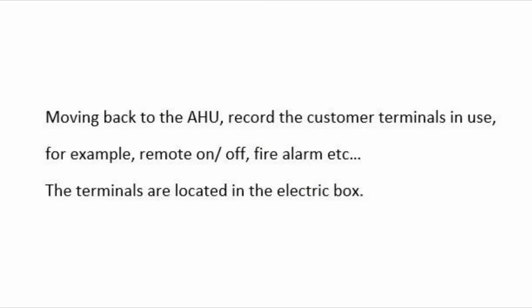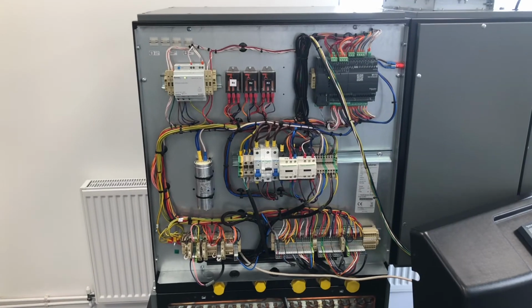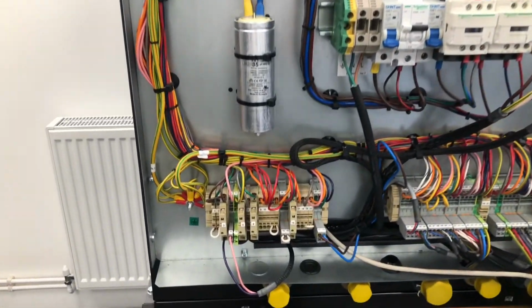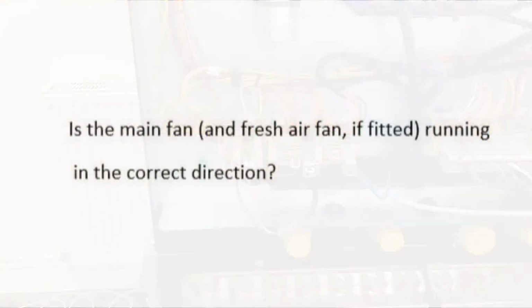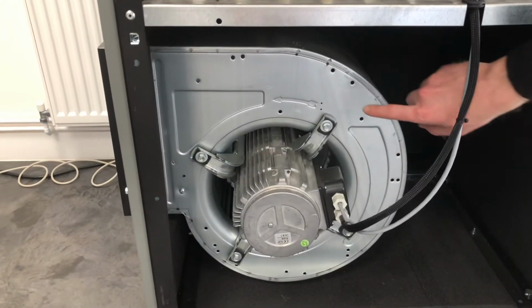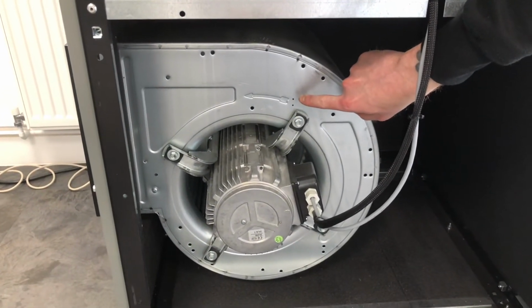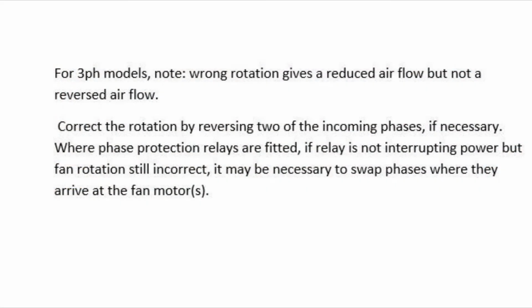Note the customer terminals in use. These are located in the bottom left-hand corner of the electric box. To ensure that the main and fresh air fan are running in the correct direction, simply check the direction of airflow against the arrow located on the side of the fan. Take corrective action should this be necessary.